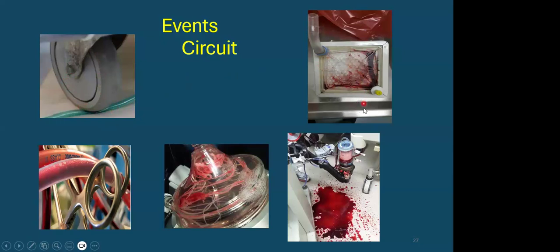Clotting of the oxygenator, inevitable. I don't believe there's any oxygenator that doesn't clot. This is what they will do. They will clot. And this is what we've seen, rinsing out an oxygenator. There's also fibrin formation. This is a different kind of pump head. This is the Levitronix CentriMag. And you can see with a large clot, chronic clot burden or fibrin, this impeller still spins. I have my doubts whether this clot burden will be accommodated in the Fresenius machine that we use. I don't think so.